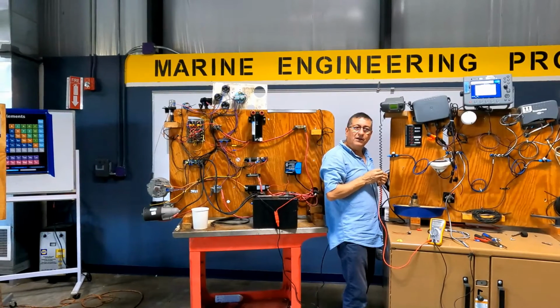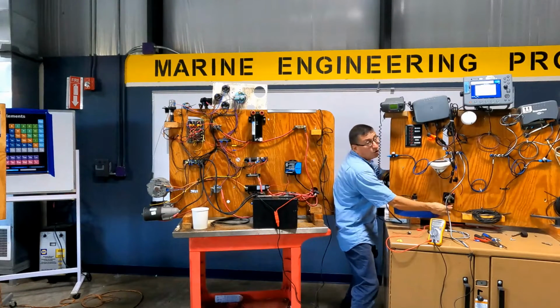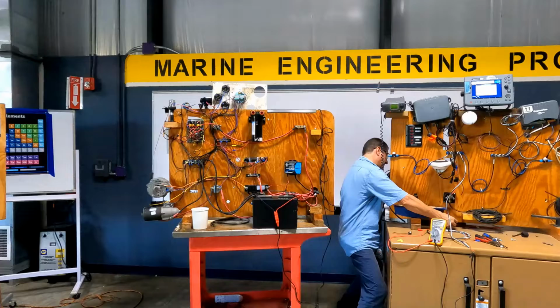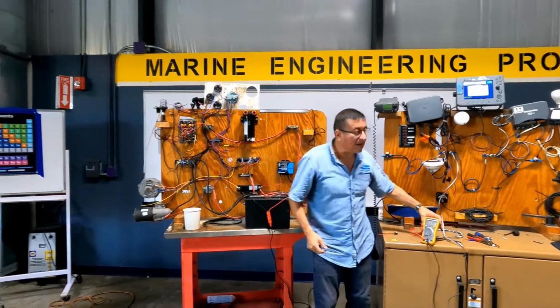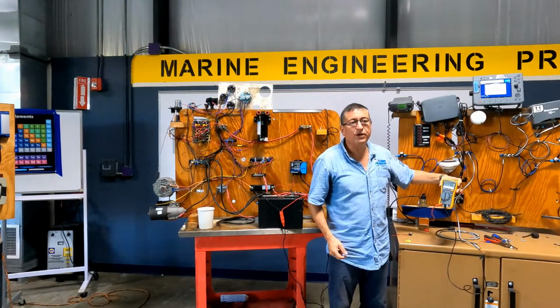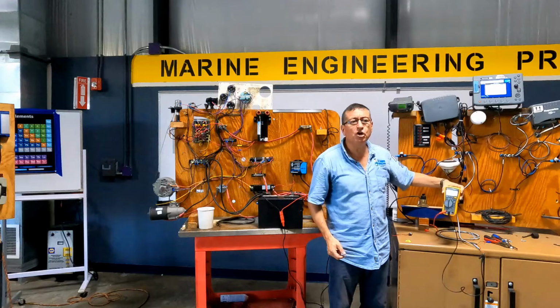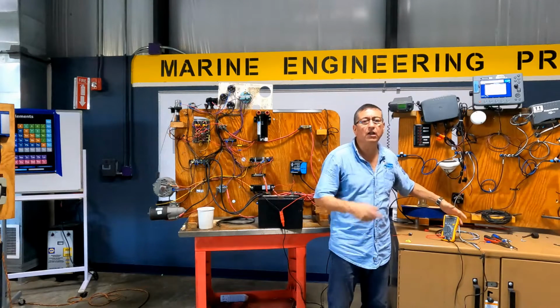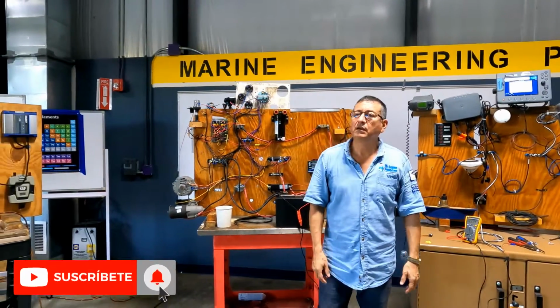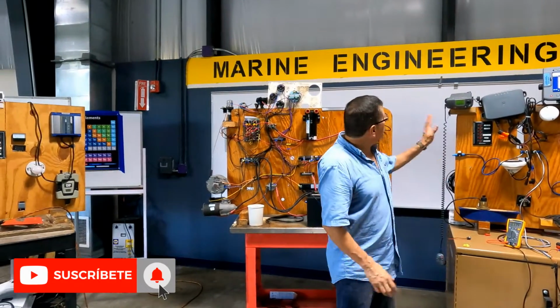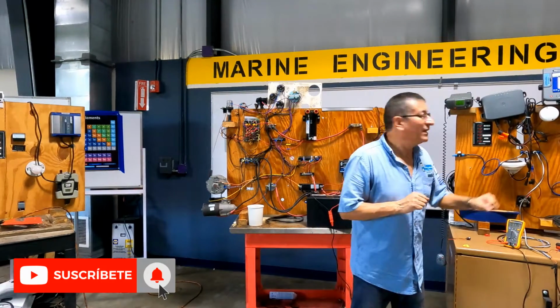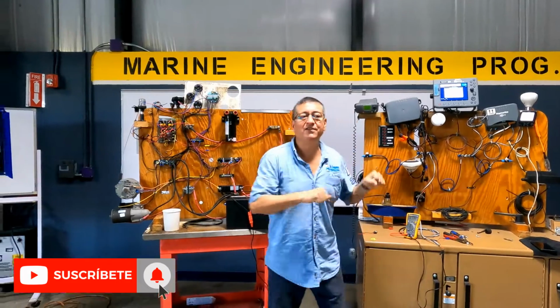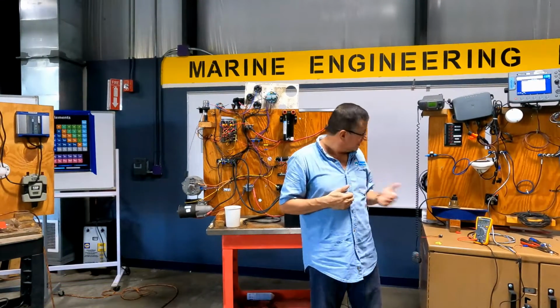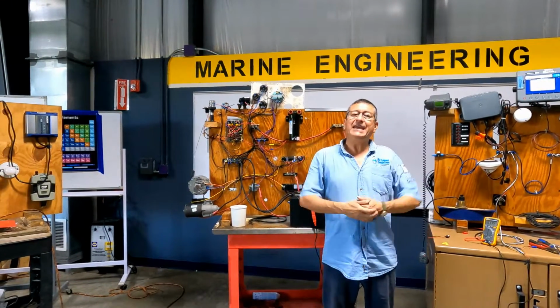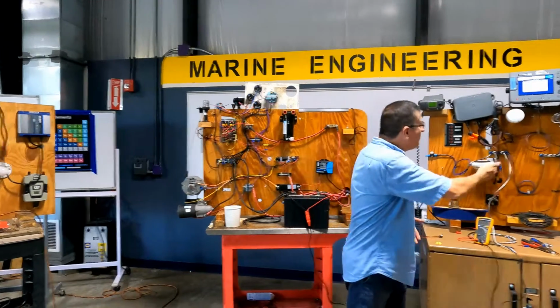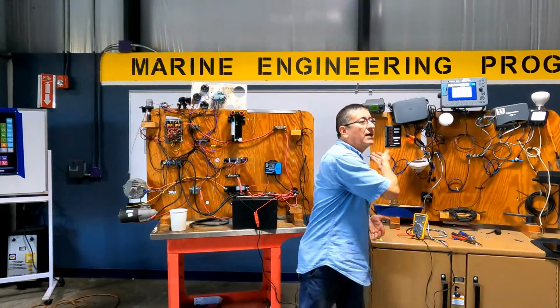Okay. I go to the positive bus bar in the panel, or to the positive of the battery in the back, and now 0.1 amps. It's good. How much is the maximum allowed? 8. In this moment it's low because I don't have the motor running, I don't have heavy equipment. 0.1. In this moment, this is the flow of amps in this backbone.